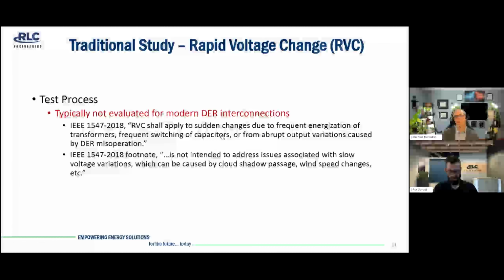This is another interesting one. We occasionally see rapid voltage change come up within system impact studies. This is not something that we typically evaluate because it's not typically a concern for modern DER interconnections. IEEE 1547 states that RVC shall apply to sudden changes due to frequent energization of transformers, frequent switching of capacitors, or from abrupt output variations caused by DER misoperation.